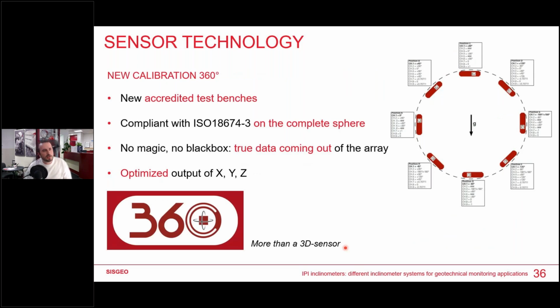Just a few words about the new calibration. We are using new accredited test benches, and we are now using this calibration for tiltmeters. So the LT-IncliBus is also benefiting from this new calibration. It's compliant to the ISO norm of the complete sphere. That means you can orient it however you want. You will always have the good accuracy, and this is due to two things. Because we don't use any algorithm, we don't use magic, we give true data because the sensor is calibrated on benches on the complete sphere. And this is why we are compliant.